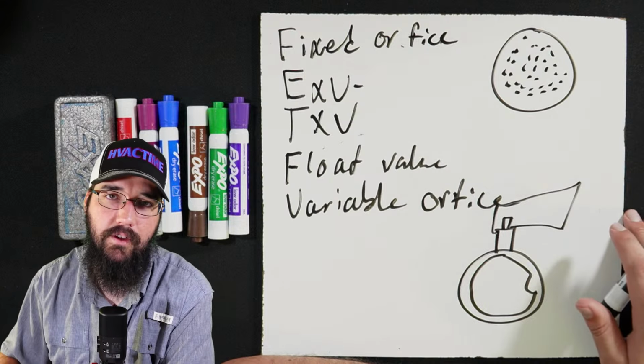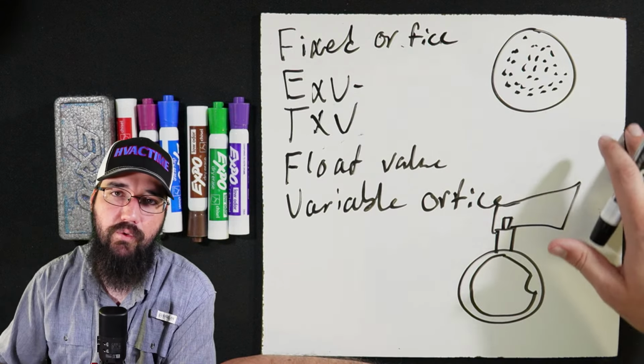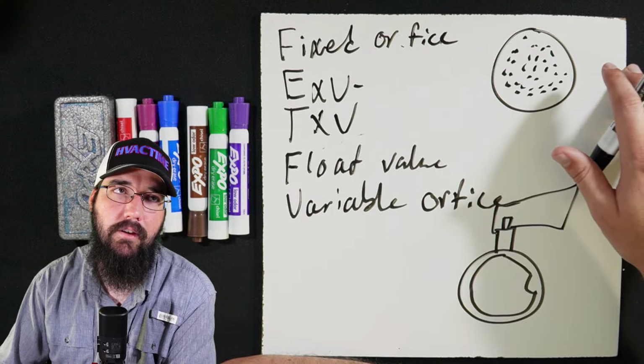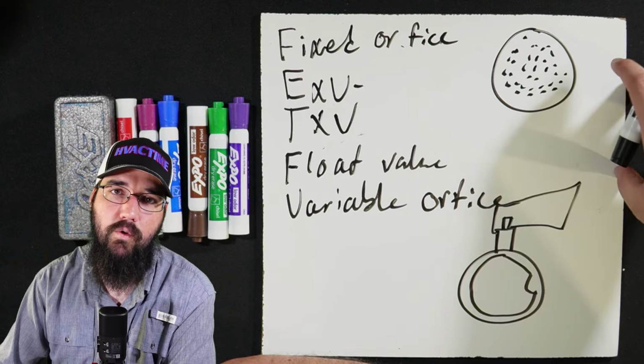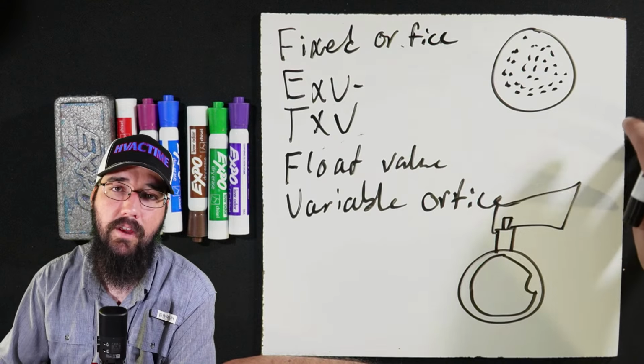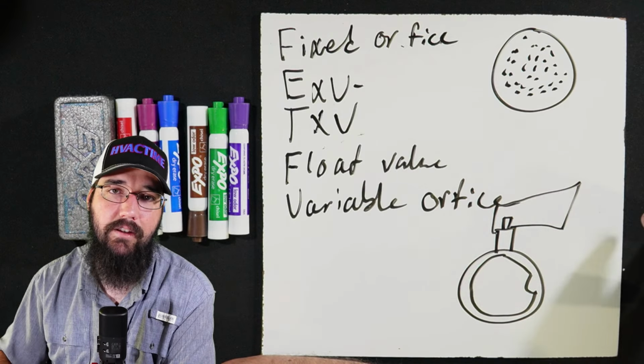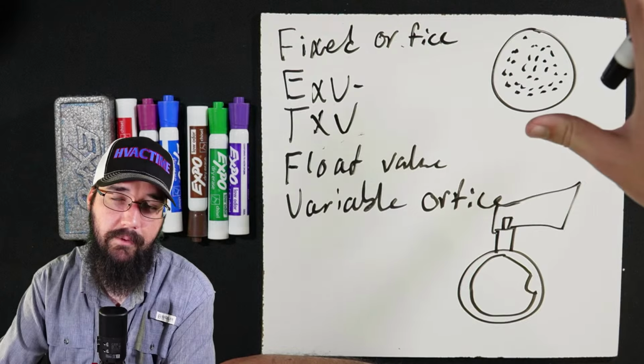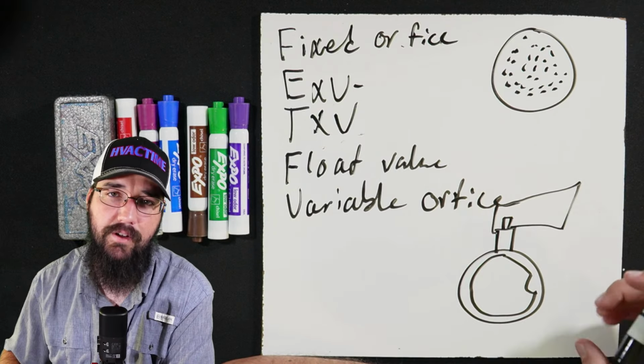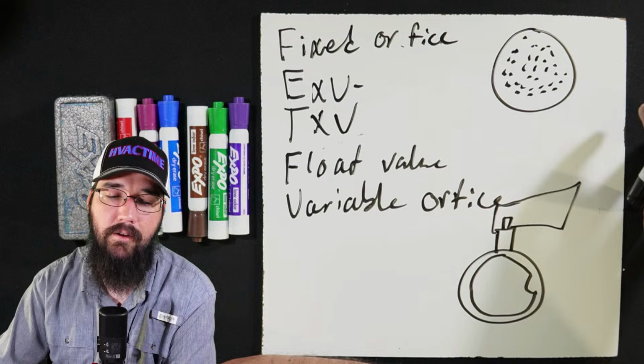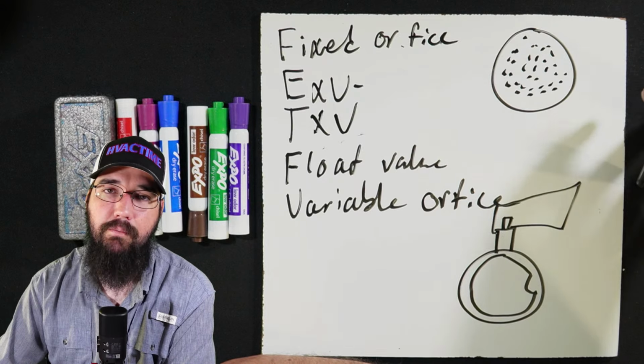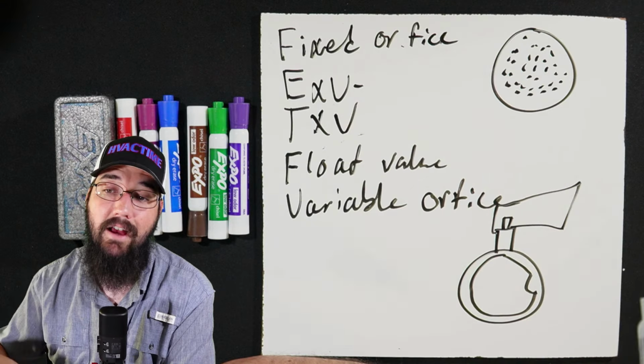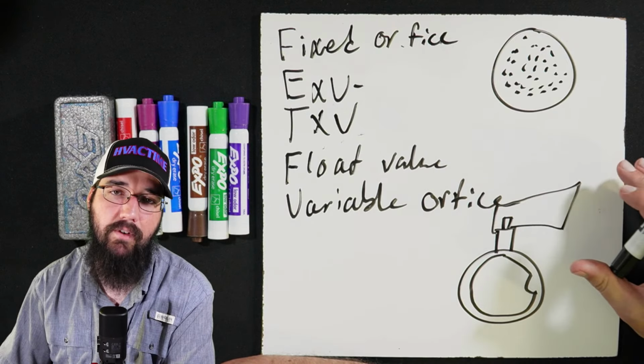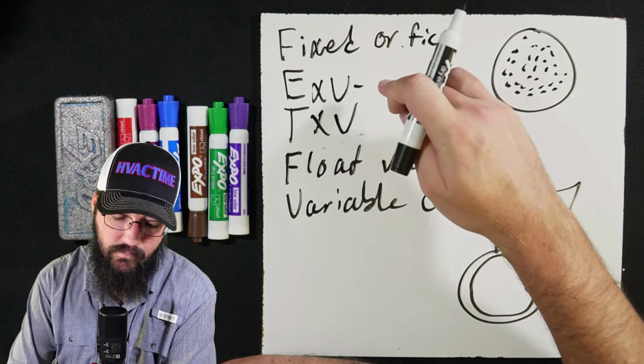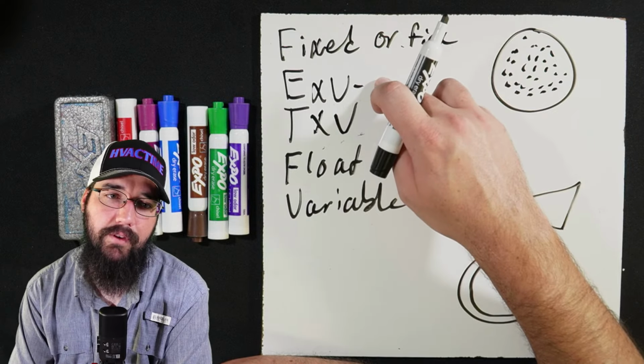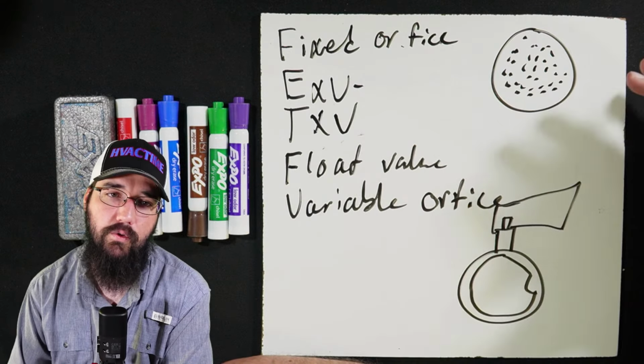Like, you even see this with RTUs. You can have really large RTUs, and the indoor coils, or the evaporator coils, will be split into multiple segments, and then we would have a valve dedicated to each segment, but they would all header off the same liquid and header back into the same suction. But we could split the load needed between multiple TXVs instead of having one just ridiculously massive valve. That's the issue we run into with EXVs. We can only go so big.